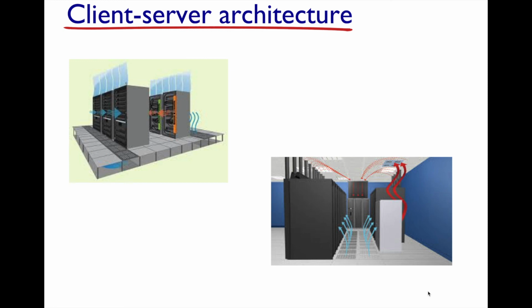Here is a depiction of one design for airflow management. When you design a data center, every last detail is engineered—down to the particulate and dust content in the air, as well as the air channels and how air flows. In this example, hot air is sucked out the top of the units, and cold air is vented in through the raised floor grates, but other designs do the opposite, with hot air wafted out one way and cold air wafted in another. If you ever get the chance to tour a data center, ask them about their airflow management—the folks who handle it will be happy to go on and on about it.